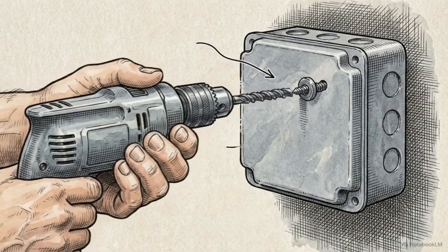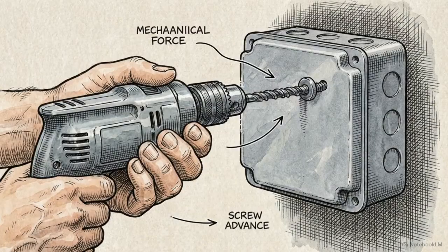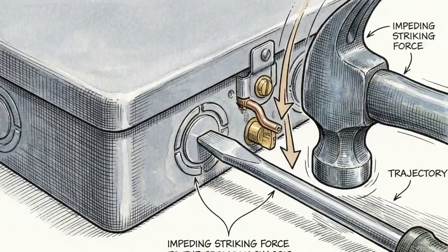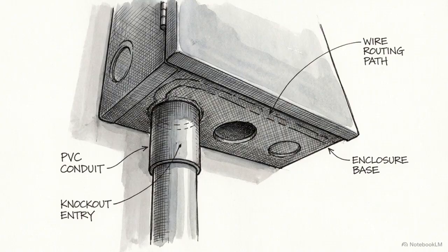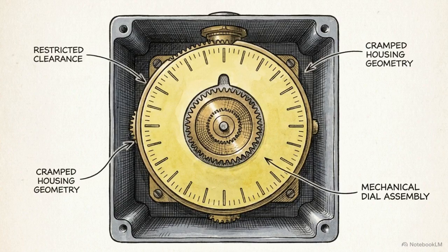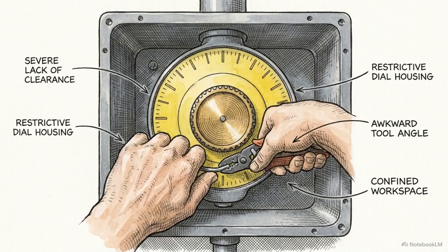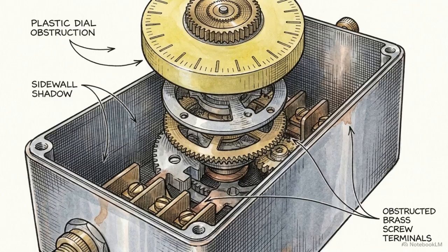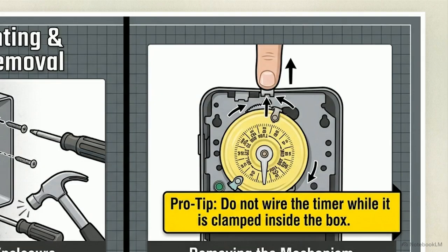With the power confirmed off, mount the metal enclosure to your wall using heavy-duty screws and wall anchors. Once it's secure, use a hammer and screwdriver to punch out the bottom or side knockouts so you can run your wire conduit. Here is a helpful tip. Trying to wire the terminals while the entire mechanism is clamped inside that restrictive metal box limits your visibility and makes the job difficult. To bypass that problem, look at the diagram here.